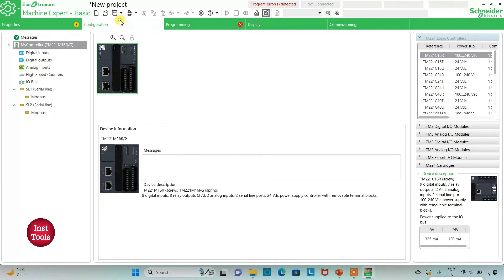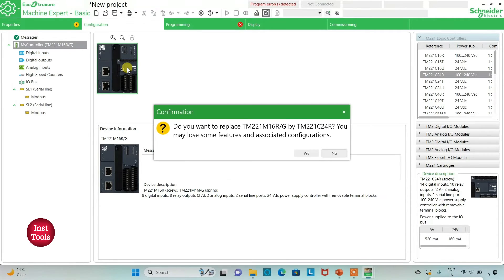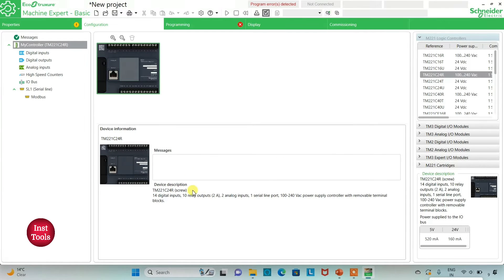After that, I will go to the Configuration tab where we have to select and configure the logic controller. Here is a list of different logic controllers. I will be using TM221C24R — I will click on it and drag it. When prompted to replace TM221M16RG by TM221C24R, I click Yes. The TM221C24R has 14 digital inputs, 10 relay outputs, 2 analog inputs, 1 serial line port, and a 100–240V AC power supply with removable terminal blocks.